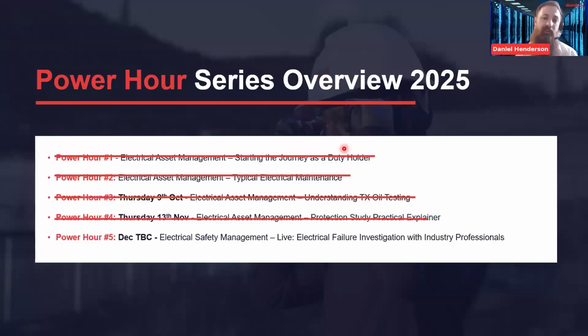We then took that to the next step on the next one, looking at typical electrical maintenance in line with sort of NFPA 70B, and then cross-referencing that against manufacturers' O&M manuals to see where those grey areas exist between NFPA 70B as a typical standard on a risk-based approach and between the manuals.